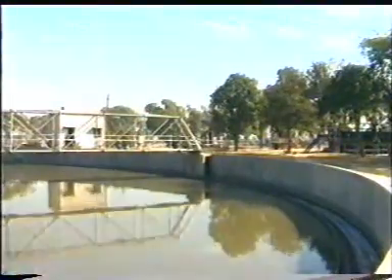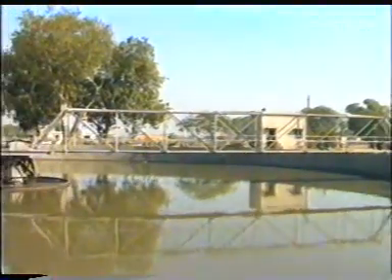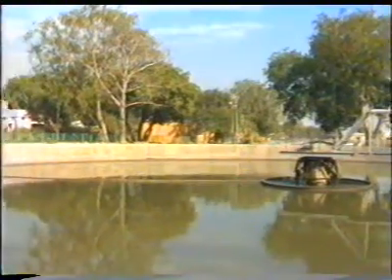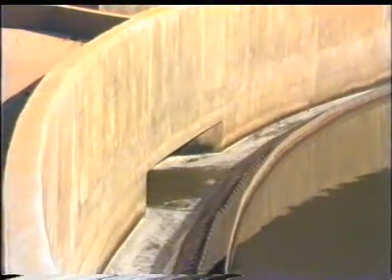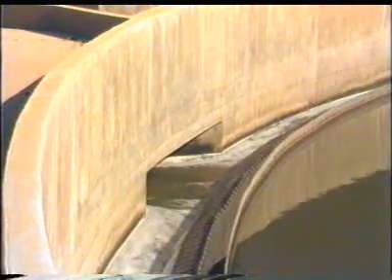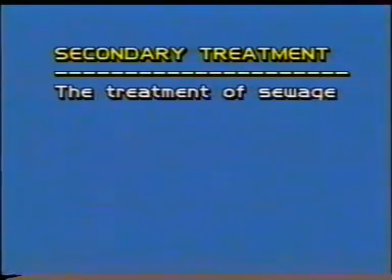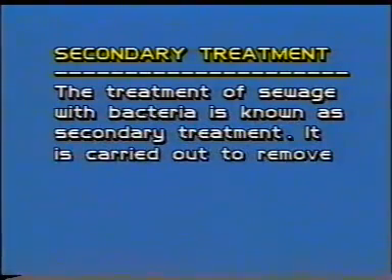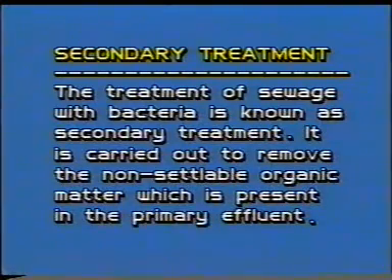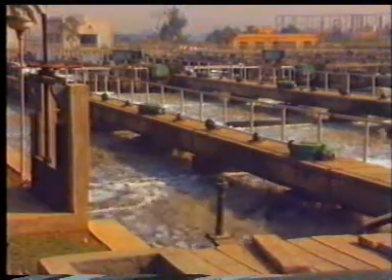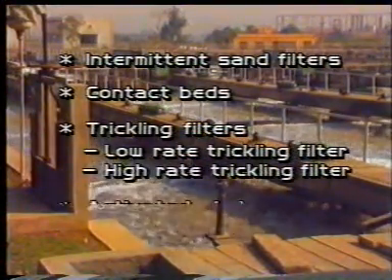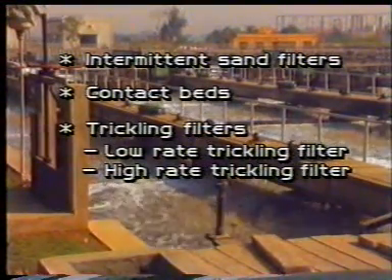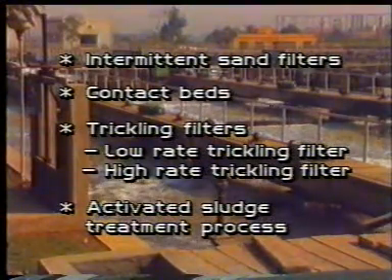Sewage treatment at the primary stage must ensure removal of sixty percent suspended solids and thirty to thirty-five percent BOD. The clarified sewage carrying mostly colloidal and dissolved solids passes out as effluent for secondary treatment. The treatment of sewage with bacteria is known as secondary treatment, carried out to remove non-settlable organic matter present in the primary effluent. The various methods include intermittent sand filters, contact beds, low-rate and high-rate trickling filters, and the activated sludge treatment process.